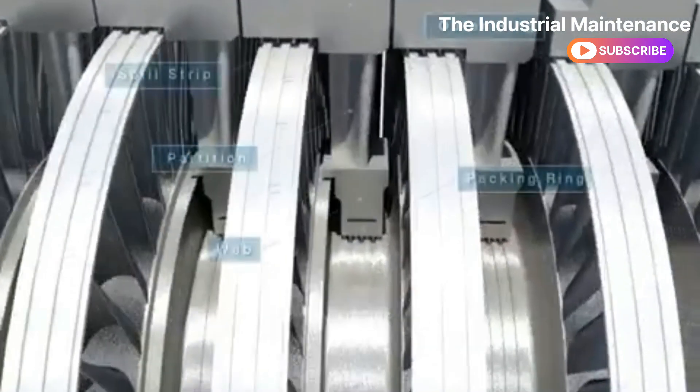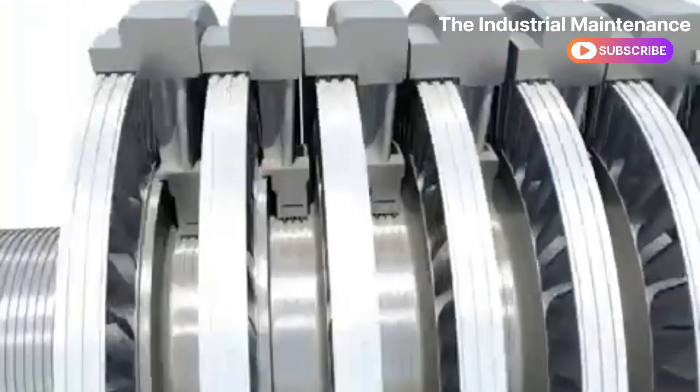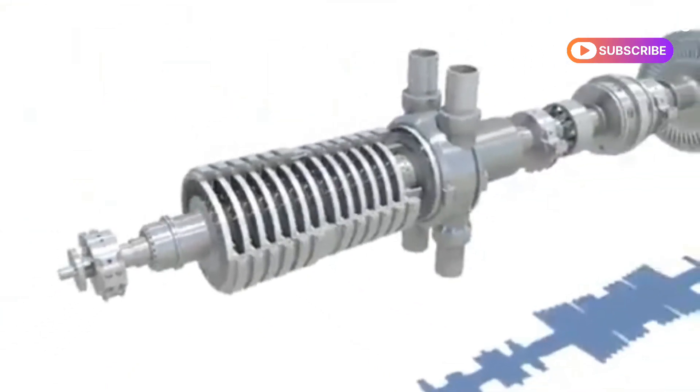The spill strip reduces leakage steam between the rear of the bucket and diaphragm, and the packing ring reduces the leakage steam between the rotor and diaphragm.